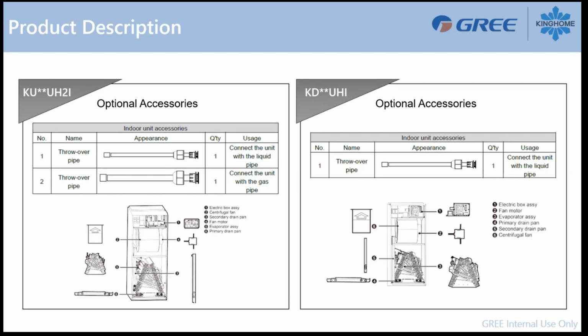Just next to it, we have the KD-UHI. This is a standard static pressure air handler. This one will come with only one flared connection. The liquid line will be flared, so you will have to braze the suction line on this one. But the construction seems similar from one to the other.